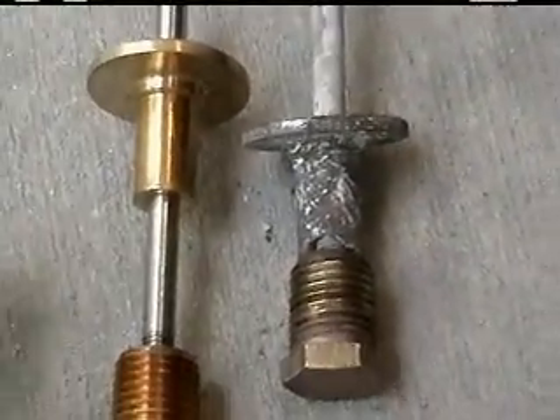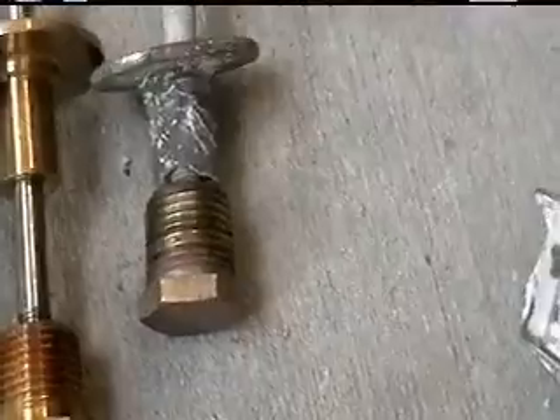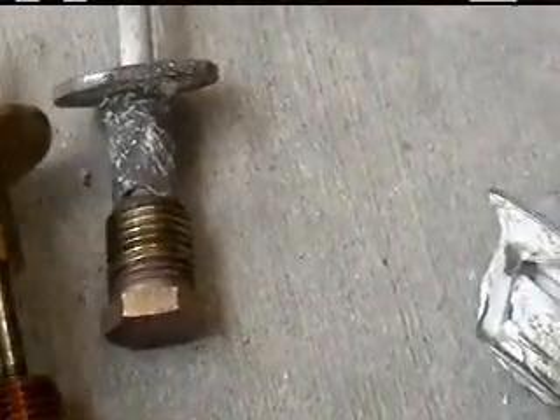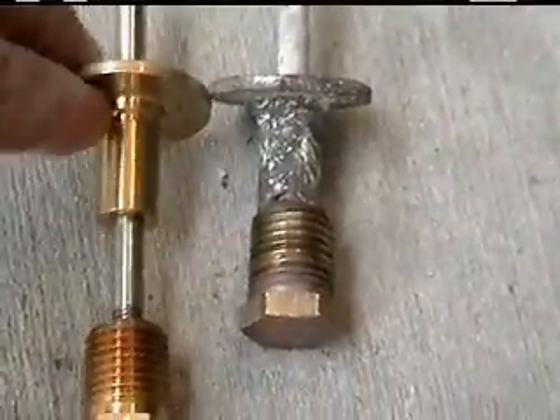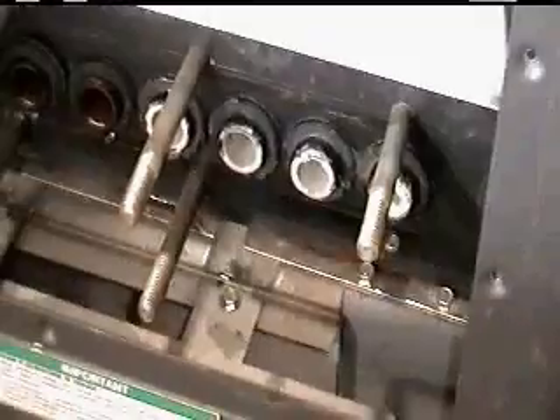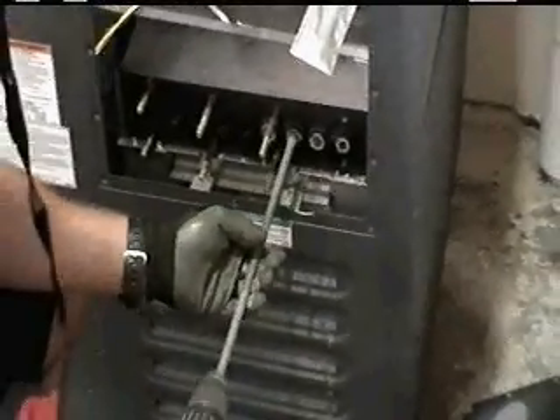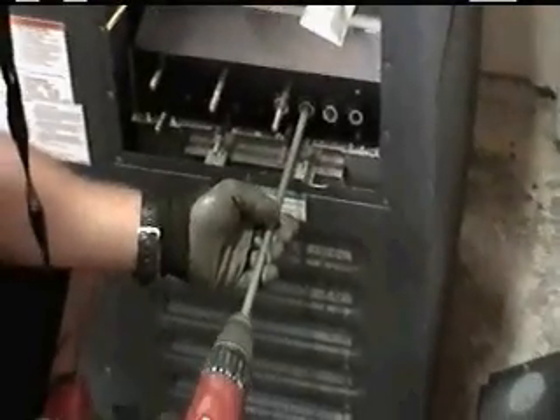Now this particular bypass valve, it's normal for these to wear out about once a year. We will get in there and replace these. This is a part that just normally wears out. That's soft brass. Now, what you're seeing there, those white rings, is actually the scaling and calcium that is built up on the inside of the heater tubes.